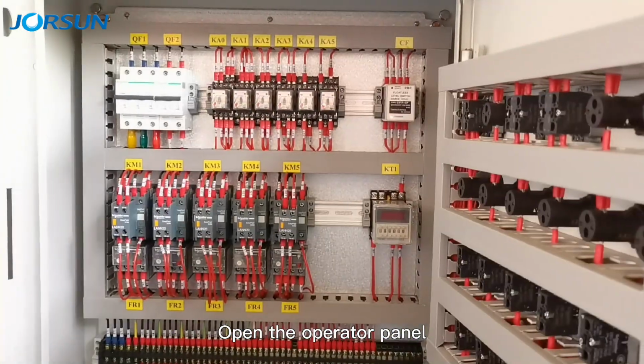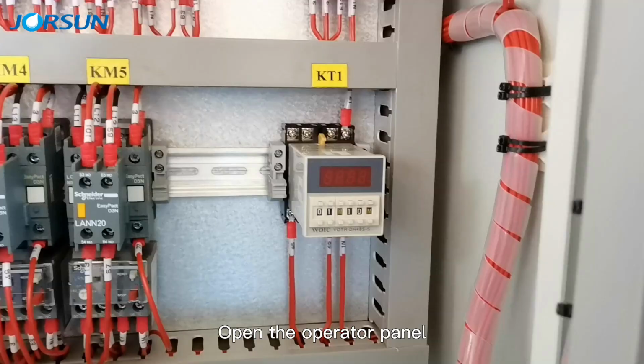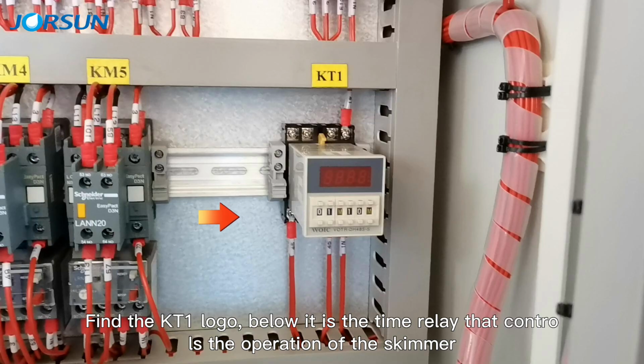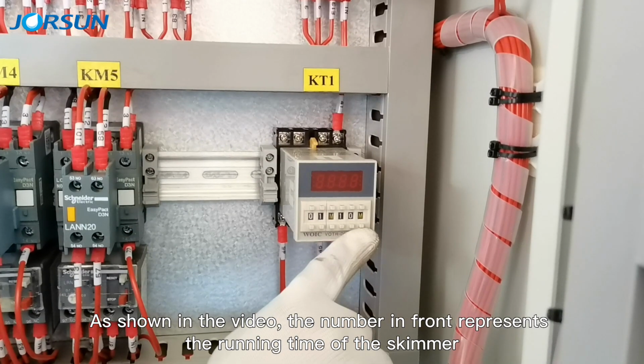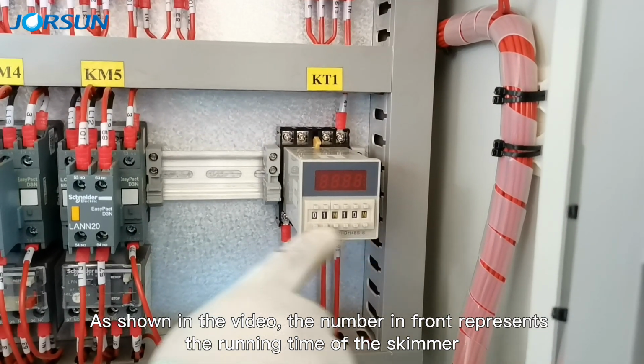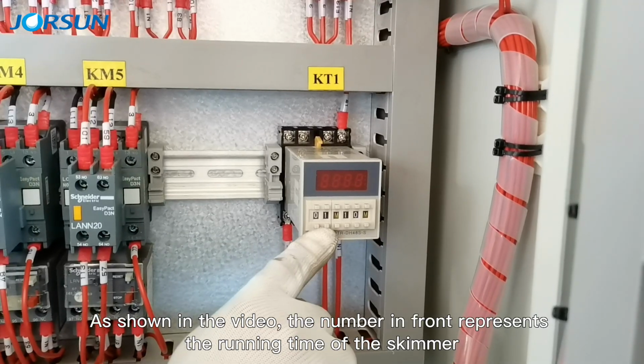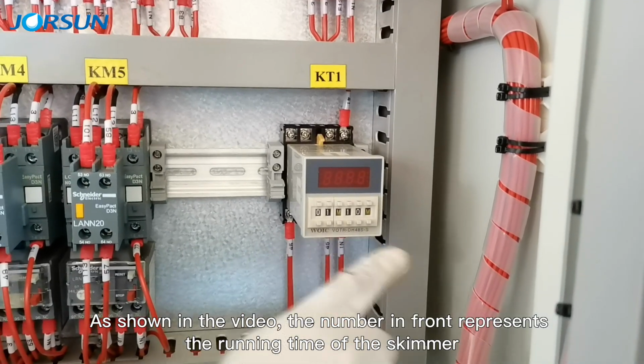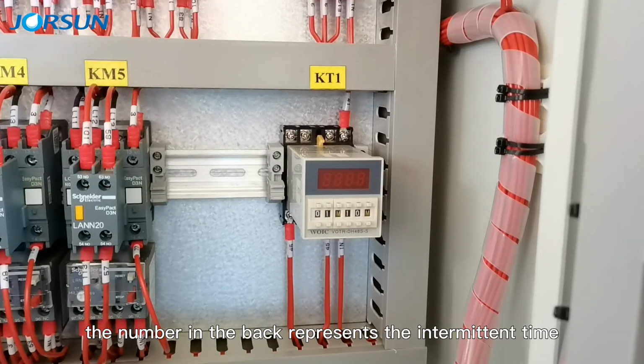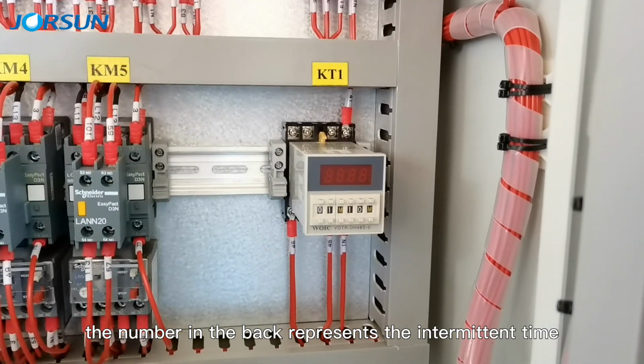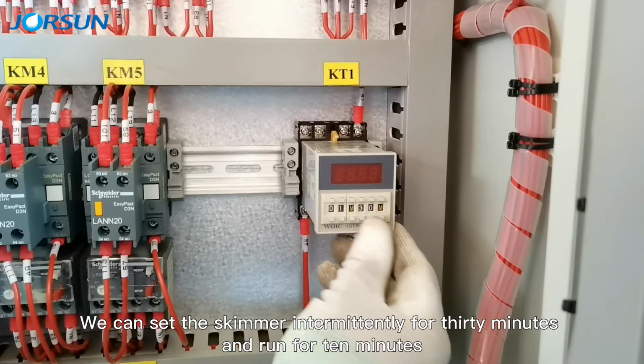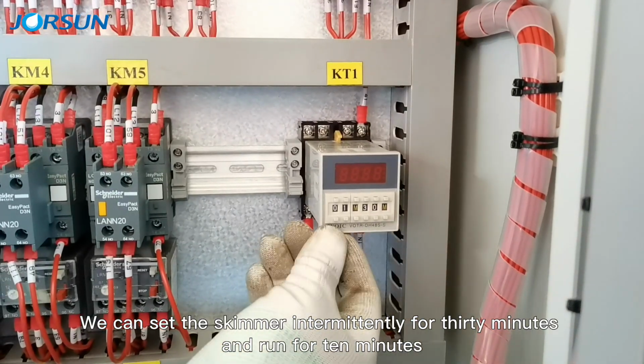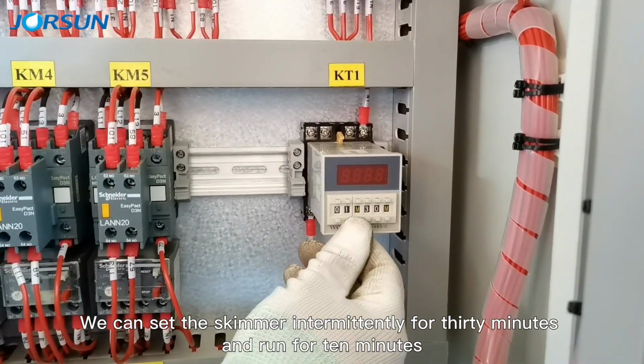Open the operator panel. Find the KT1 logo. Below it is the time relay that controls the operation of the skimmer. As shown in the video, the number in front represents the running time of the skimmer. The number in the back represents the intermittent time. We can set the skimmer intermittently for 30 minutes and run for 10 minutes.